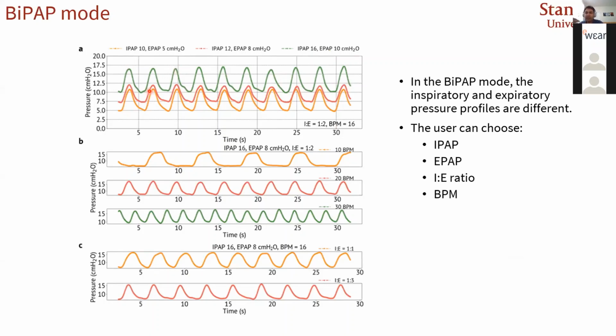It essentially helps the breathing. So when you are exhaling, it reduces the pressure. And there are a bunch of different settings you need to apply depending on the patient. And we showed that we can actually get different EPAP profiles. Also, we can vary the breaths per minute, and also IE ratio. So these are essentially what you will get in a commercial BiPAP machine.